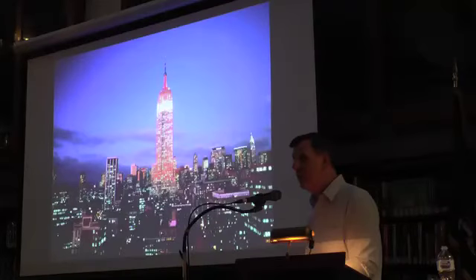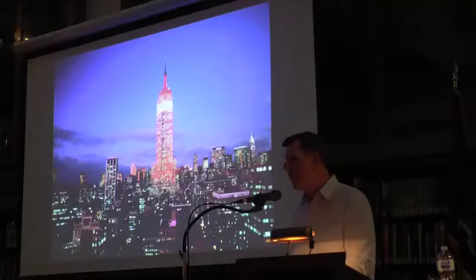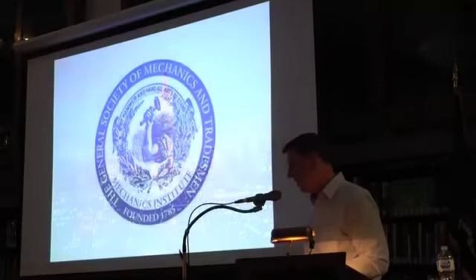What's in your building? Why are we running 5 pounds in Mrs. McGillicuddy's 3-bedroom house? Because the air's not getting out, because the air vents are bad, or the steam traps are bad, and some knucklehead's got a screwdriver that won't turn counterclockwise. That's why. So none of this is complicated. All of this is pretty easy to understand.